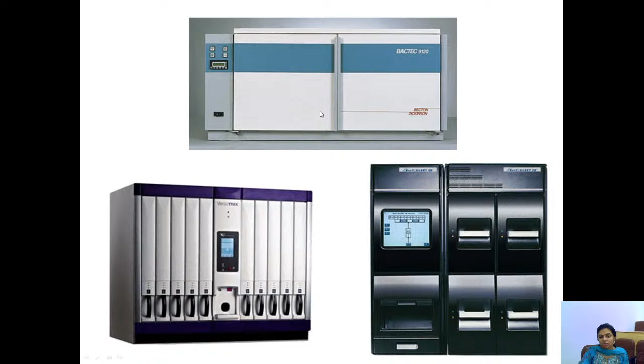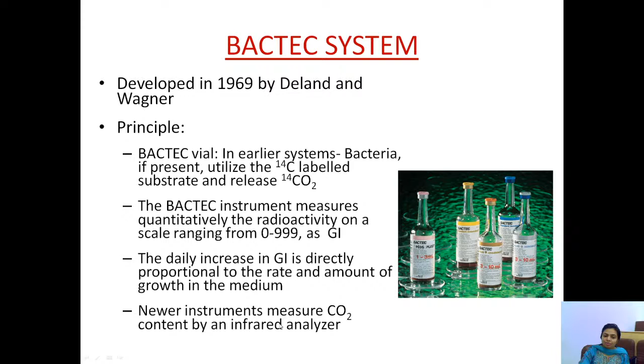Now the BACTEC vial. What is the principle of the earlier system? In the BACTEC vial, if bacteria are present, they utilize a radiolabeled carbon 14 substrate. The natural carbon number is 12. So the 14C-labeled substrate is metabolized and releases radiolabeled carbon dioxide. The instrument quantitatively measures the radioactivity on a scale from 0 to 999 as a growth index. The daily increase in the growth index is directly proportional to the rate and amount of growth in the media. Newer instruments measure the carbon dioxide content by an infrared analyzer.